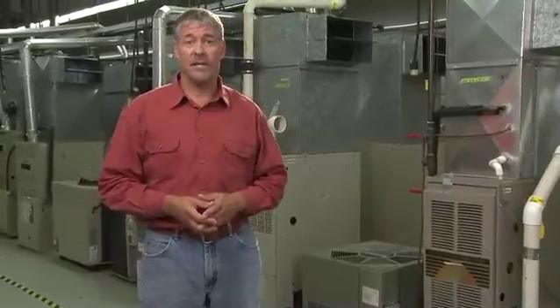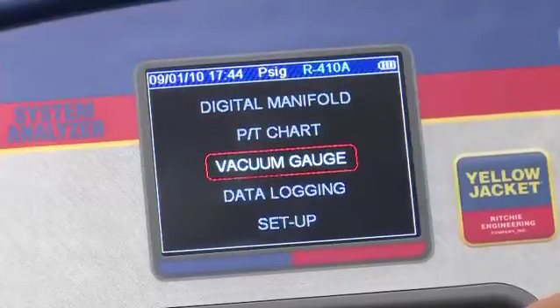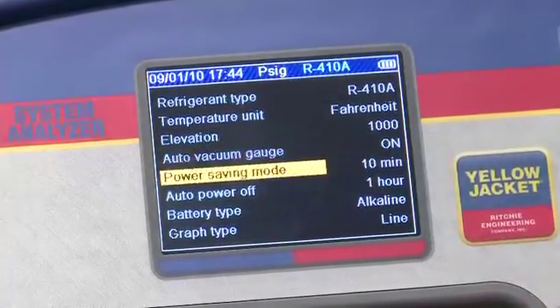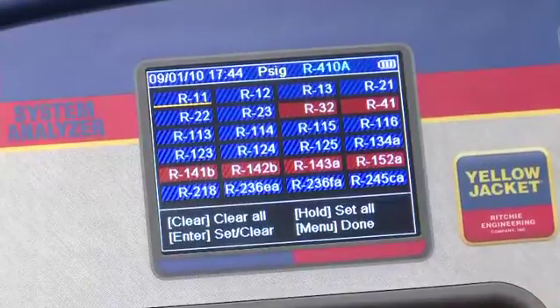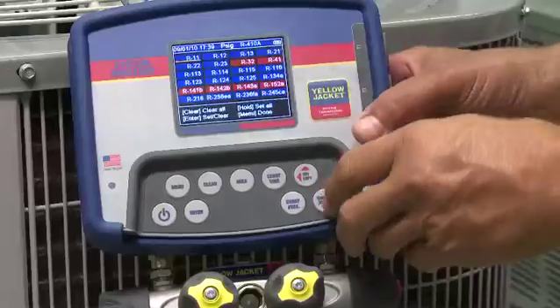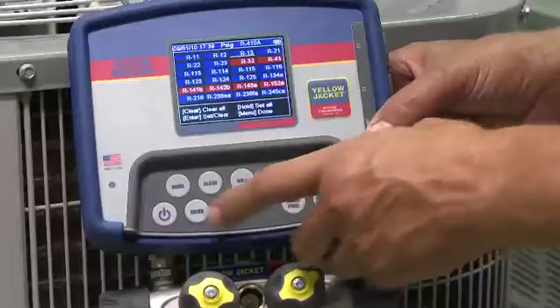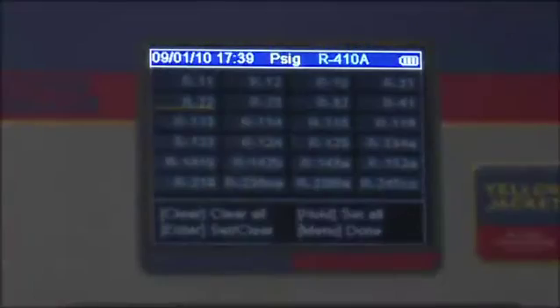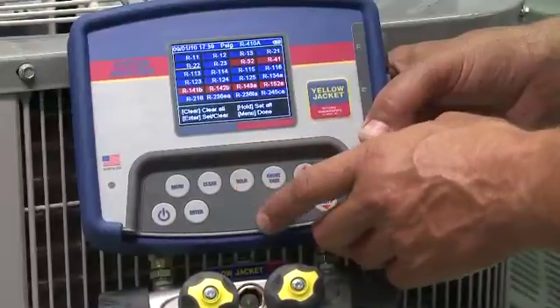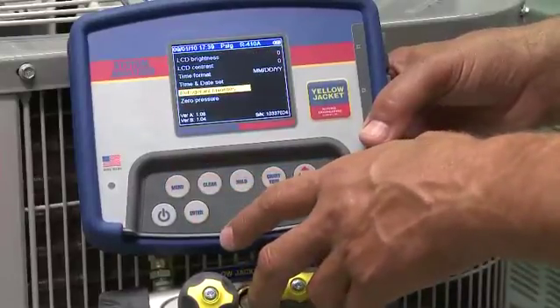When you get to refrigerant, you have the option of setting up a favorites list so you can reduce your list to the refrigerants you use the most. Set the list by going to the setup menu and scrolling to refrigerant favorites. All of the refrigerants are currently set as favorites, indicated in blue — red if they're flammable. Move the yellow cursor with the arrow keys to the refrigerants you don't want as favorites and press enter. They'll turn gray and will no longer appear on your quick search screen. If you want to reactivate them as favorites, press enter again. The clear key will clear all favorites except the active refrigerants shown at the top of the manifold screen, and the hold key will set all refrigerants as favorites. Once you're done selecting your favorite refrigerants, press the menu key to save your changes and return to the previous screen.